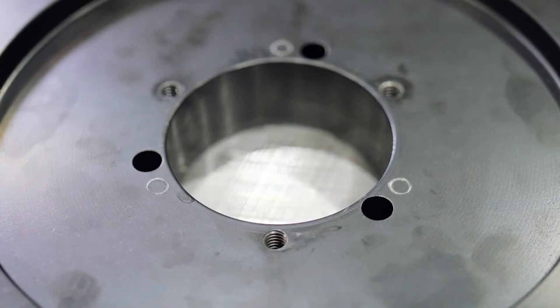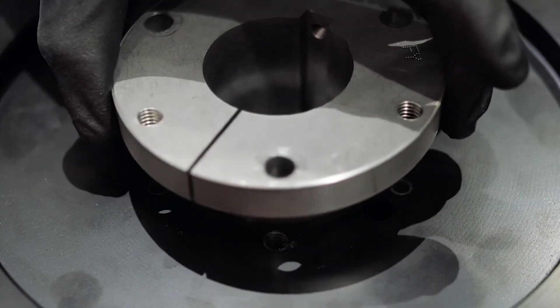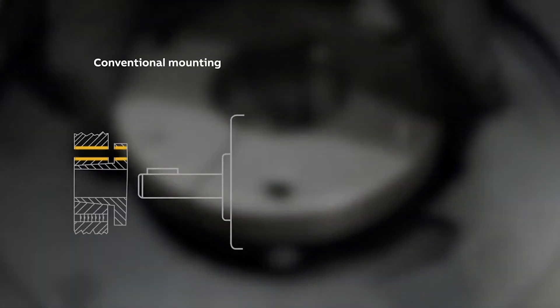Insert the bushing into the hub. QD bushings can be mounted in two different ways: conventional or reverse mount.